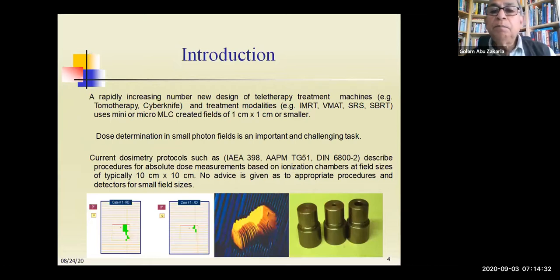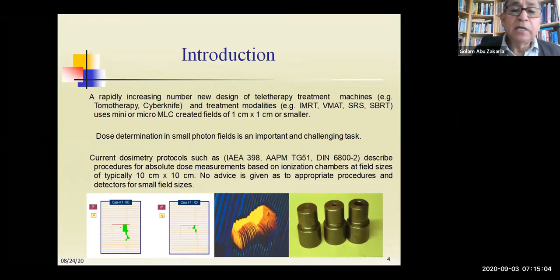But in our time, there is a rapid increase of new design radiotherapy machines, especially, you know, the Gamma Knife and CyberKnife, and many new treatment modalities like IMRT, VMAT, SRS, SBRT, which use mini or micro MLC, creating fields less than 1 by 1 centimeter. And the dosimetry of these small fields is challenging work. And current protocols, like IAEA 398, AAPM TG-51, and DIN 6800-2, are a few of the many protocols in the world, designed based on the ionization chamber at a 10 by 10 field. In these protocols, which are used all over the world, no advice is given for the procedures for small field sizes.